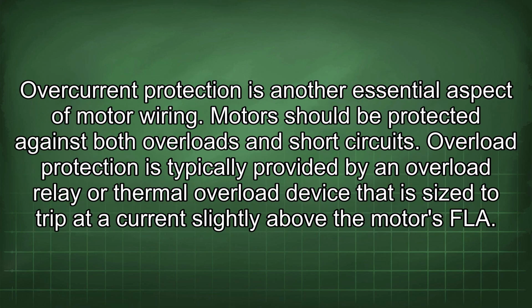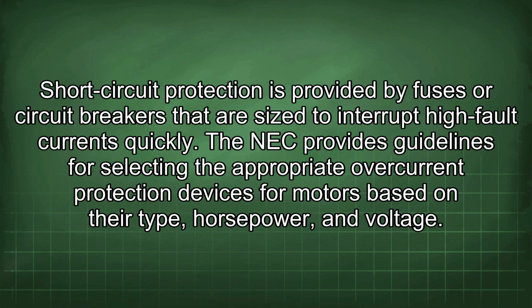Overcurrent protection is another essential aspect of motor wiring. Motors should be protected against both overloads and short circuits. Overload protection is typically provided by an overload relay or thermal overload device that is sized to trip at a current slightly above the motor's FLA. Short circuit protection is provided by fuses or circuit breakers that are sized to interrupt high fault currents quickly. The NEC provides guidelines for selecting the appropriate overcurrent protection devices for motors based on their type, horsepower, and voltage.